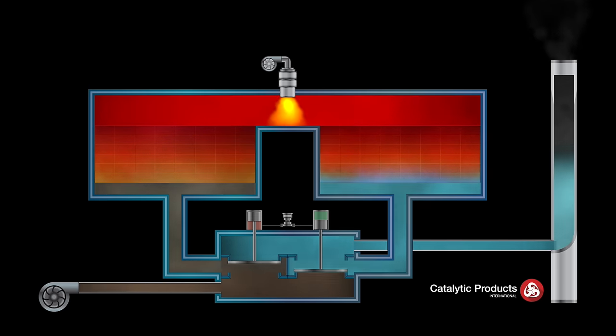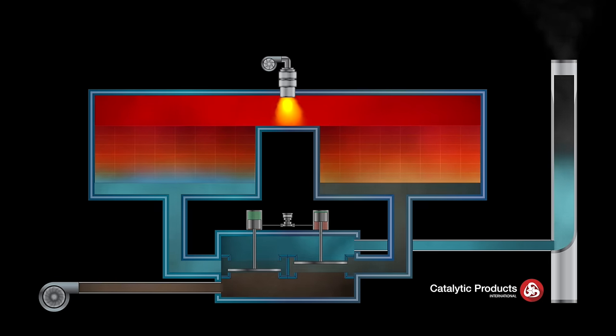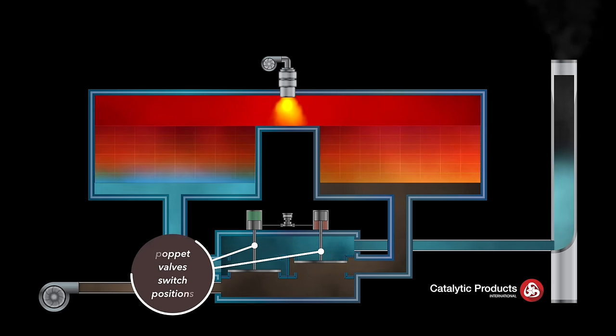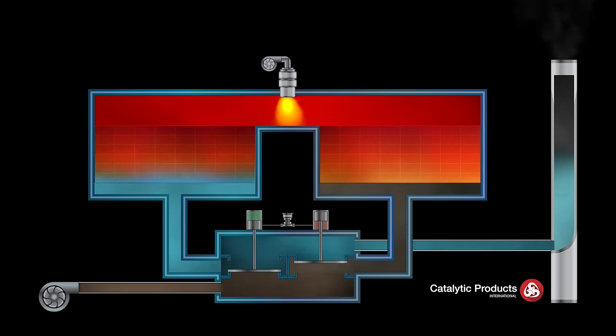Every three to six minutes, the process of airflow reverses direction as the poppet valves switch positions, allowing the heat captured in the ceramic media from the exiting clean air to heat the incoming process air.